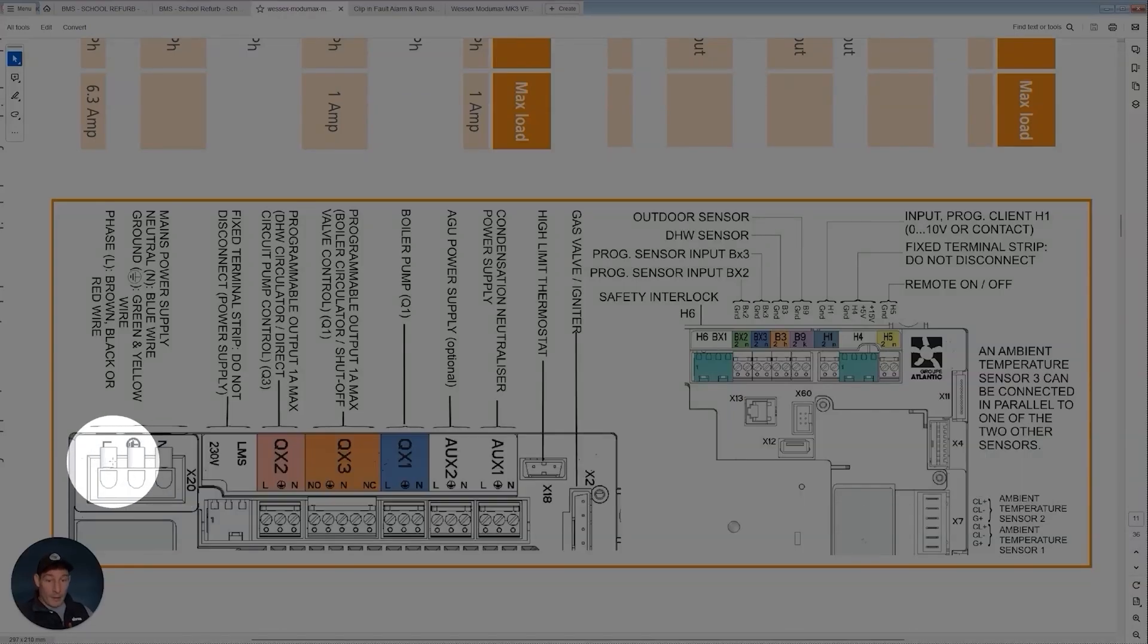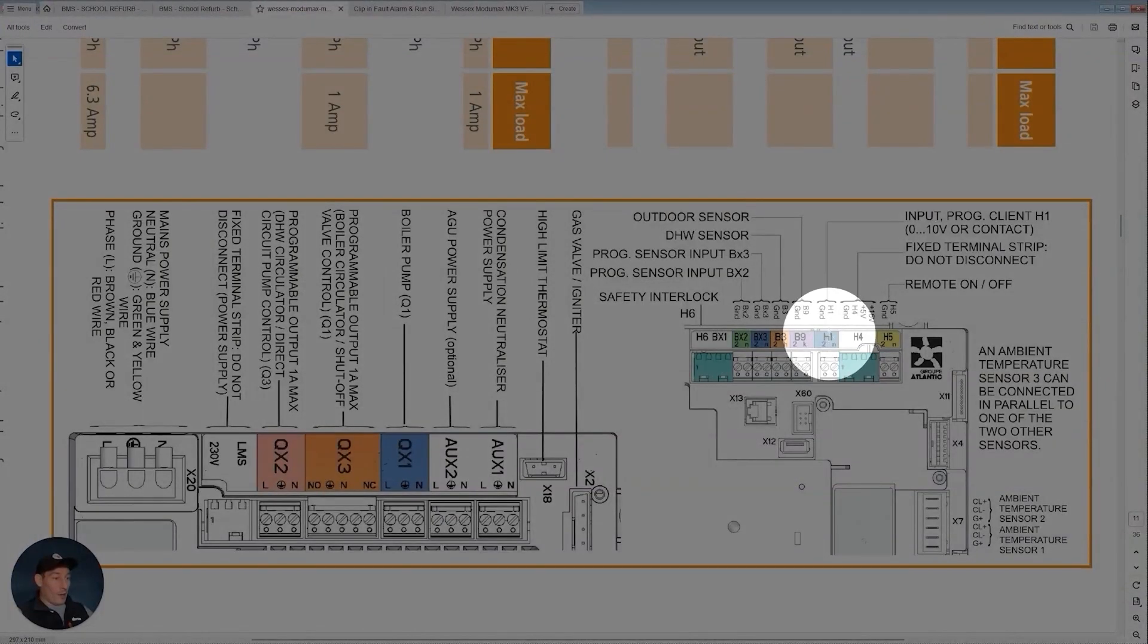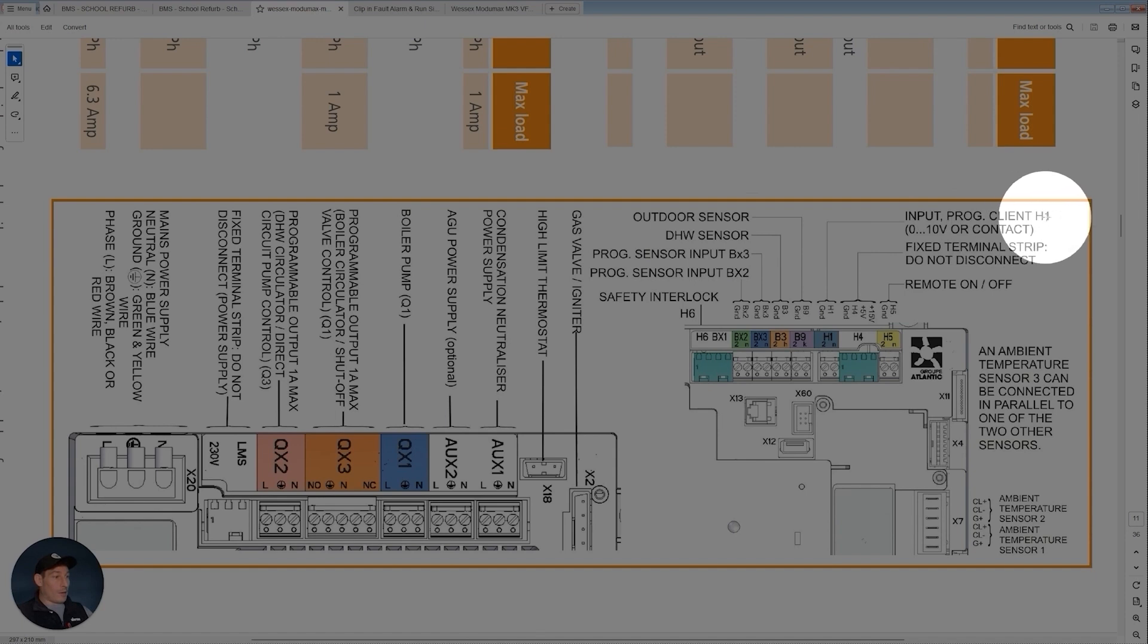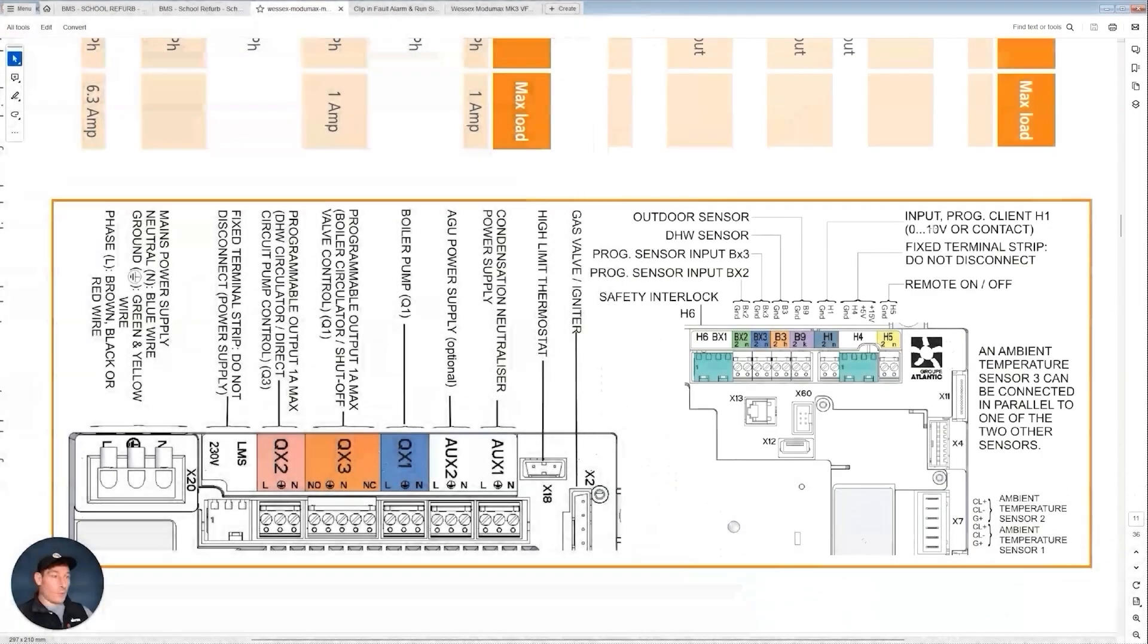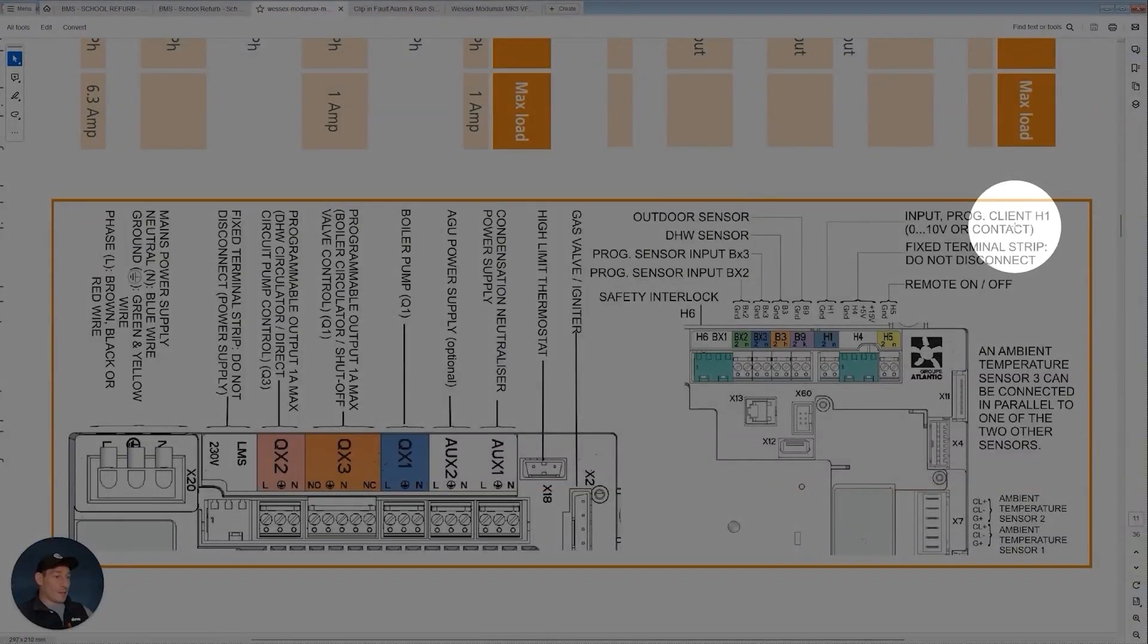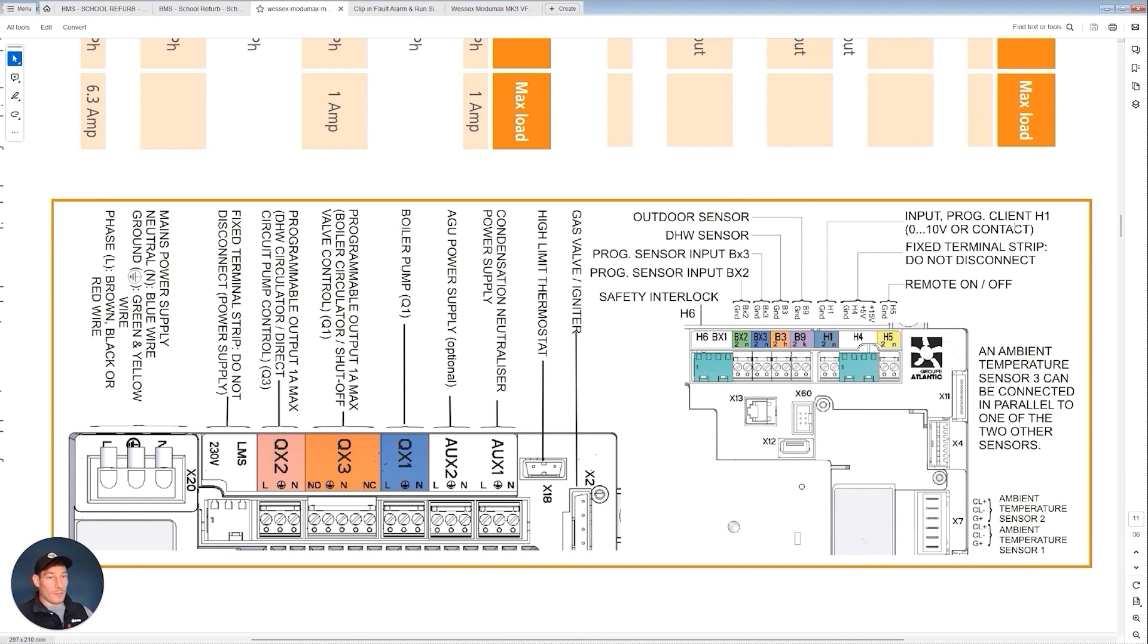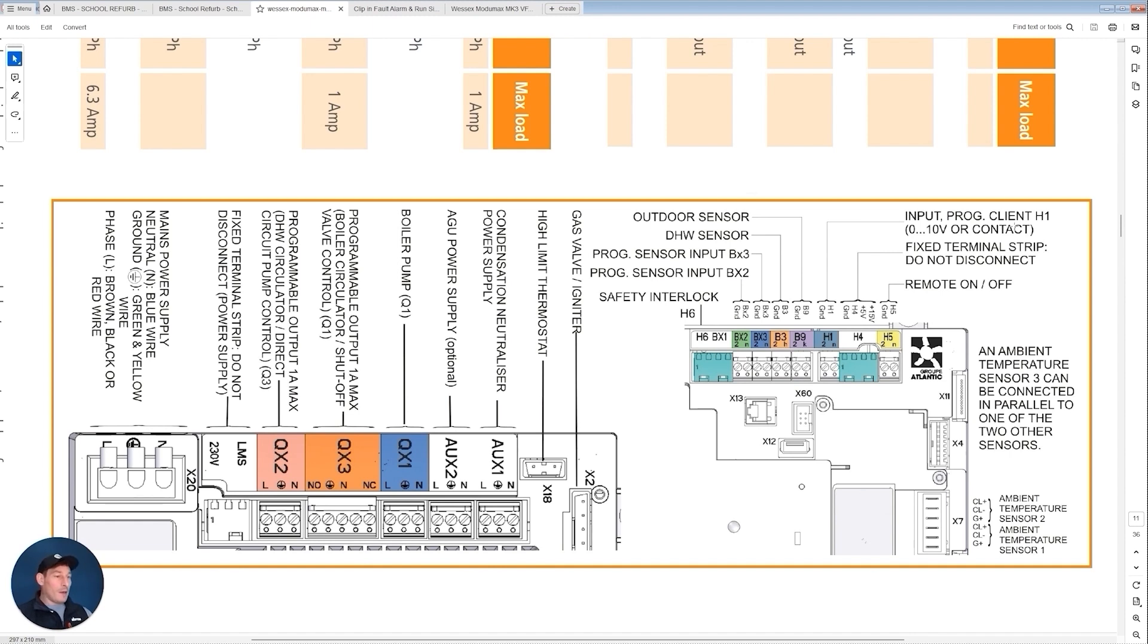So H1 here—input prog client H1—basically what that's saying is the 0 to 10 volt signal which we just talked about, or contact, so it's just an on-off signal like most people are used to. But if you read the spec we also need to take an enable output signal of the boiler and a fault signal output of the boiler, so a signal into our BMS, our control system, to let us know when the boiler is enabled and when it's in fault.